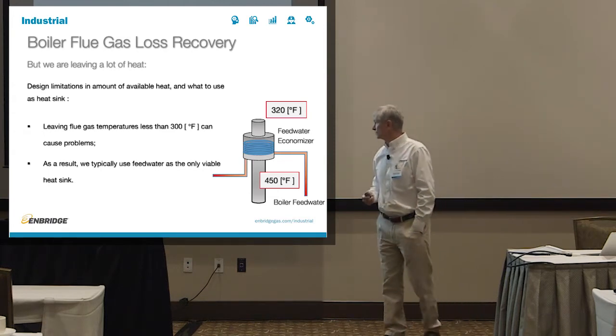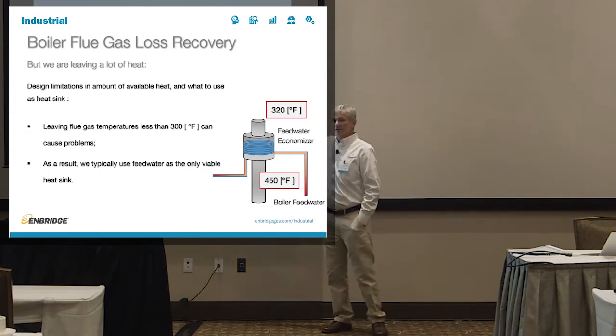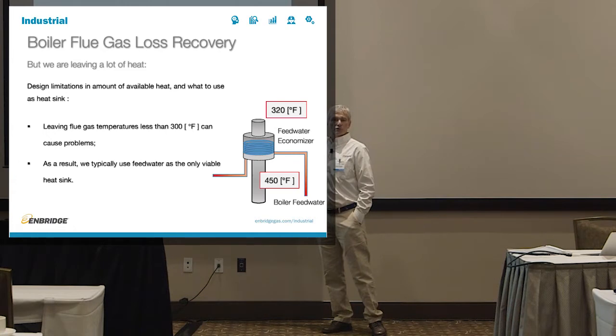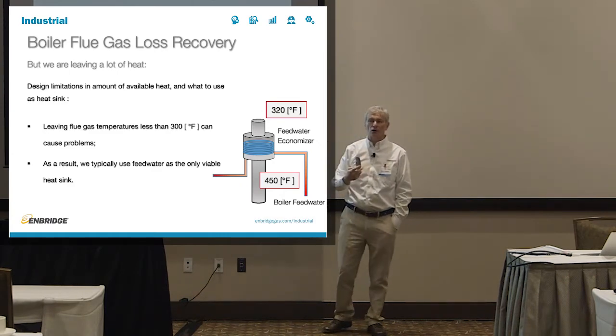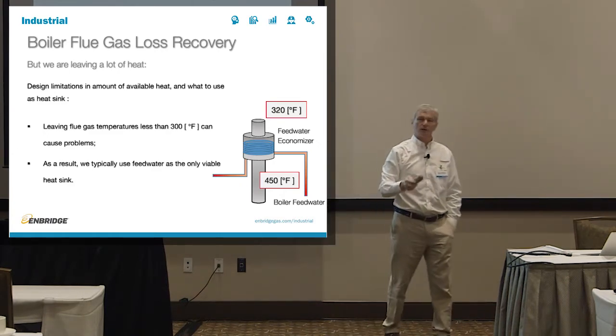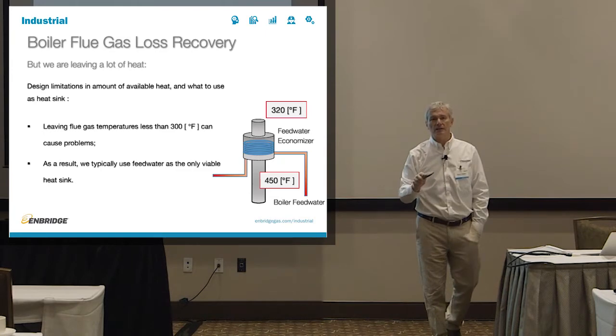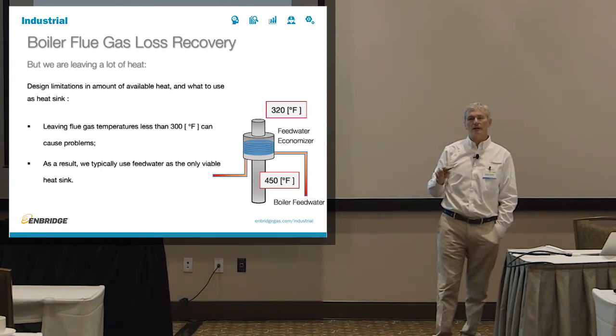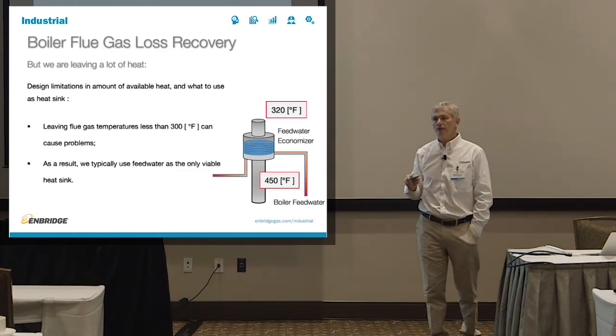The other limitation is, because feed water economizers are inexpensive, they don't have any special stainless steel materials or something like that. So you really don't want anything to condense in them. So what happens is you're limited on that. You can only use feed water through this. That's why it's called feed water economizer, because putting anything colder in there could risk condensing in the economizer and ruining your economizer really quickly.